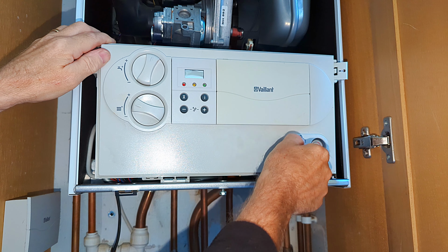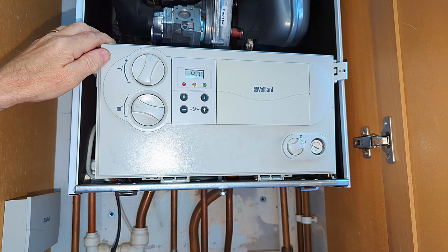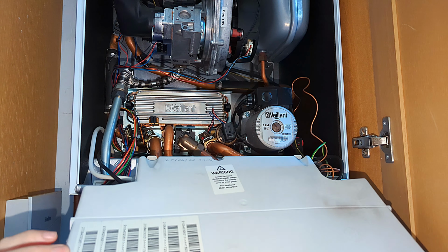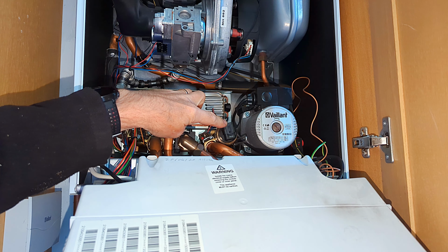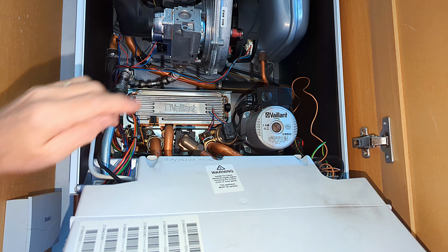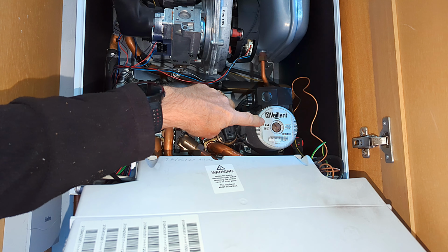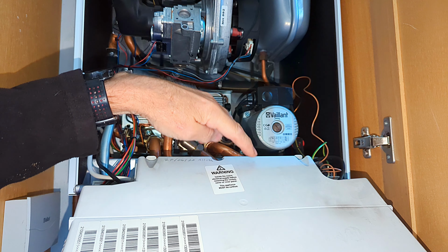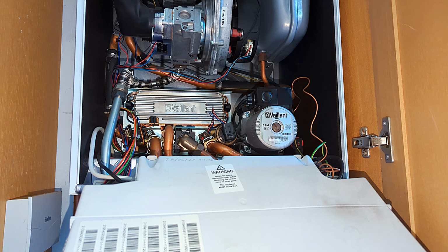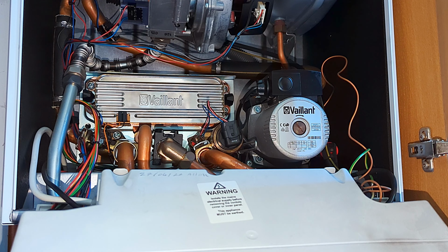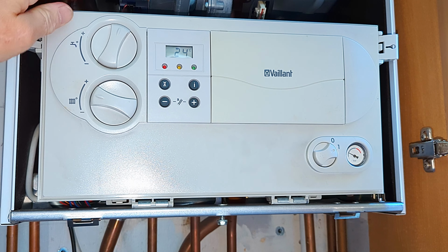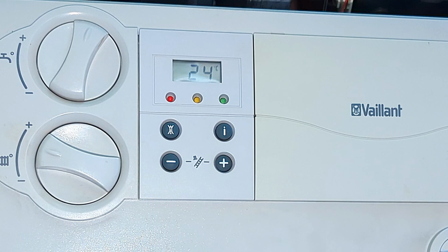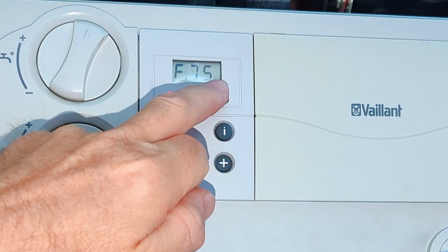One of the ways to tell if your pump is running is when you turn your boiler on or you press the reset button, the boiler will operate the motorized valve, which is what you can hear now. And then we'll hear a click on the relay from the circuit board as it tries to run the pump. And if you don't hear a humming sound after the click from the relay, that's a good indication that your pump is not running. The boiler will try several times to run the pump, and when it doesn't see a pressure rise on the pressure sensor, it would then trip out with the F75 fault. And there we go, it's now tripped out with F75.